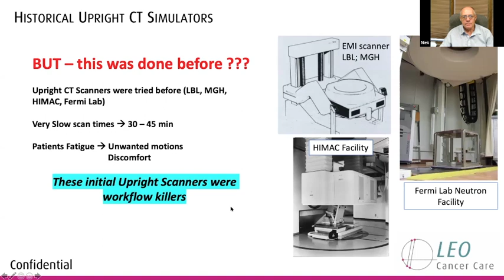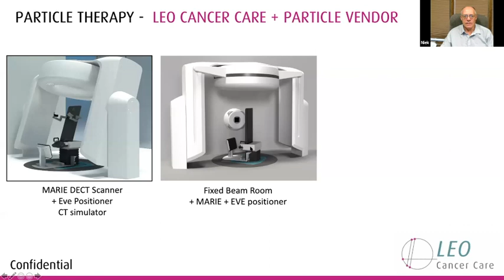So I call these scanners a great idea, but really workflow killers. Because if it takes you 45 minutes just to scan a patient, by that time the patient is tired and fatigued. So now we came with a Marie dual energy CT scanner. This picture just shows the machine used purely as a diagnostic scanner outside the treatment room. It has the same patient positioner, but you can then put that same system inside the treatment room, for example, in a fixed proton beam. And this ring can come down right at isocenter and scan the patient at isocenter, retract, and treat the patient.